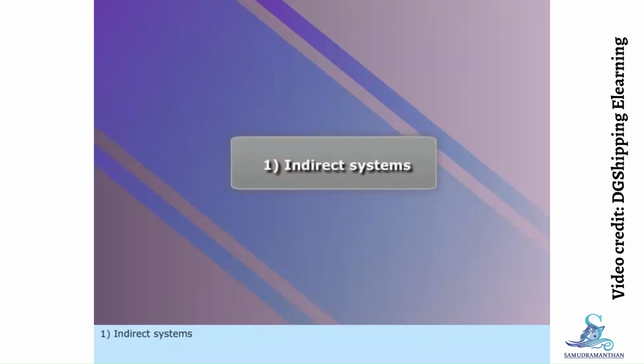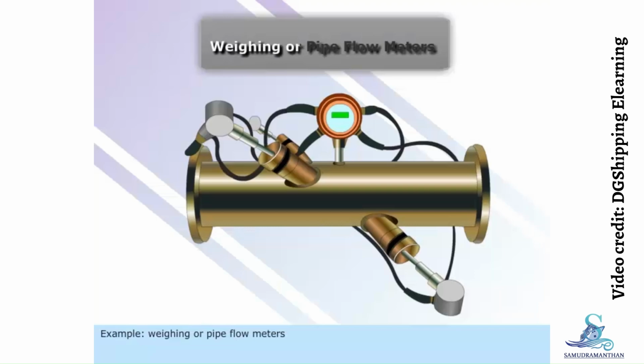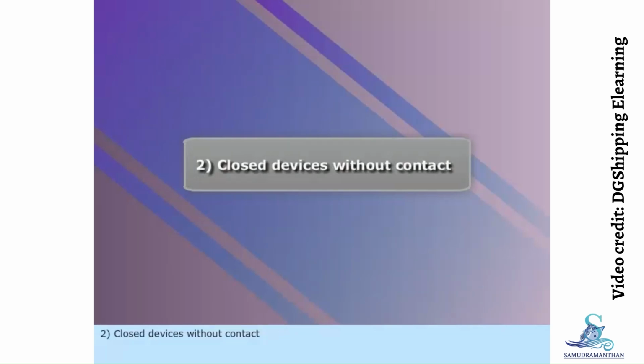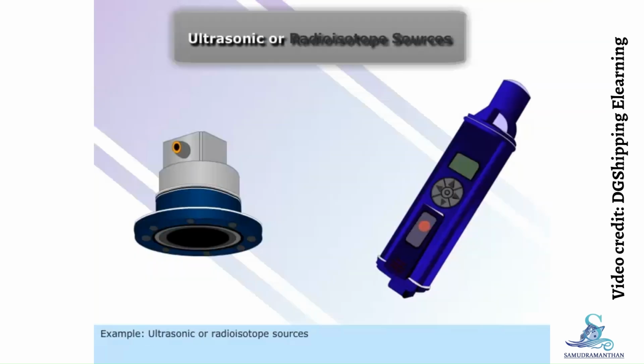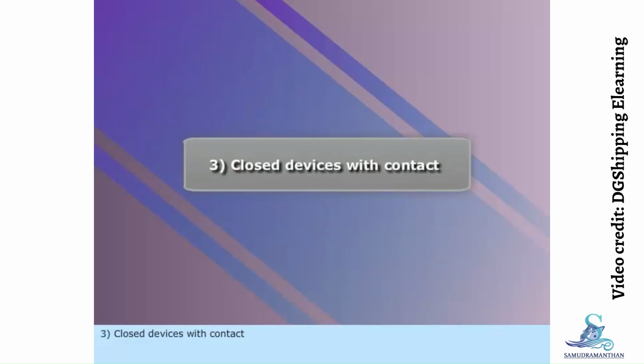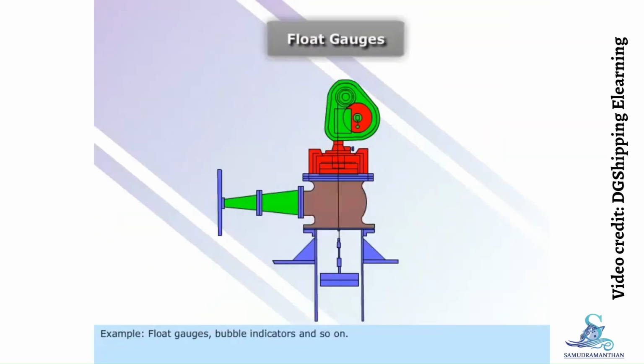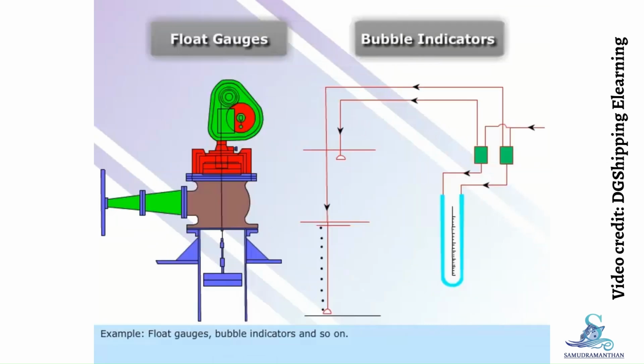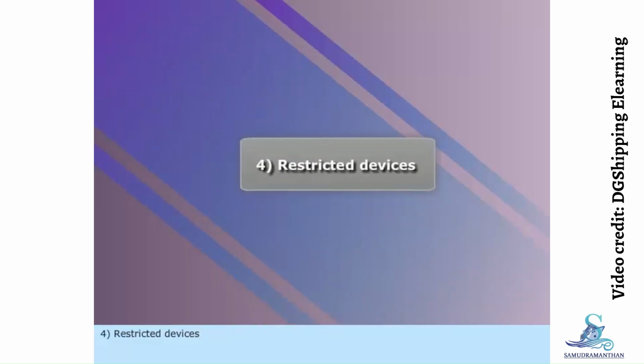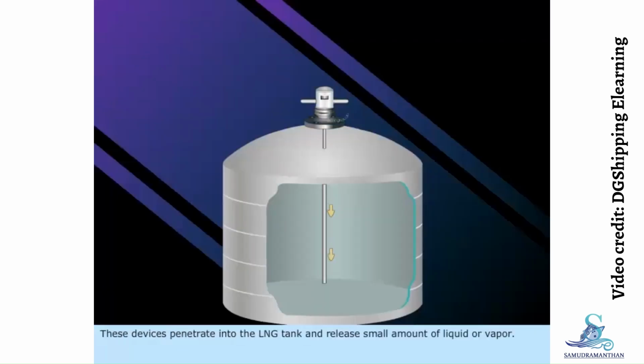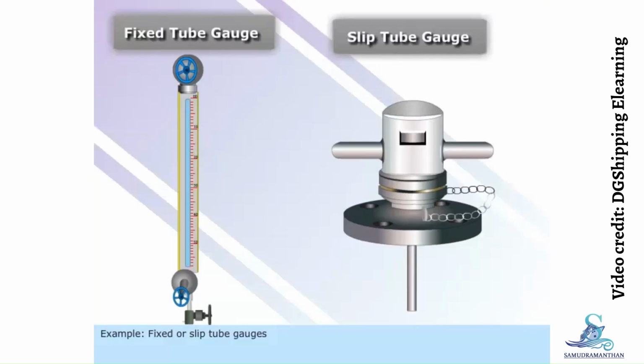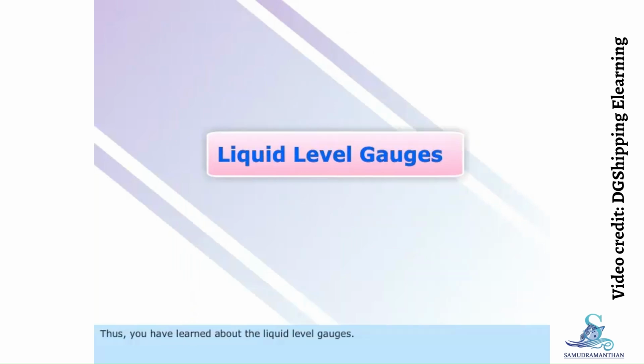1. Indirect systems. Example: weighing or pipe flow meters. 2. Closed devices without contact. Example: ultrasonic or radioisotope sources. 3. Closed devices with contact. Example: float gauges, bubble indicators, and so on. 4. Restricted devices. These devices penetrate into the LNG tank and release a small amount of liquid or vapor. Example: fixed or slip tube gauges. Thus, you have learned about the liquid level gauges.